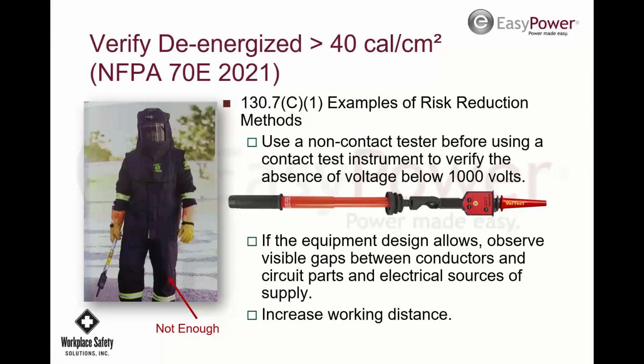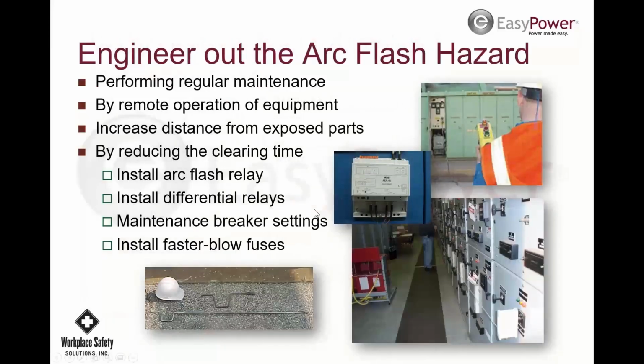So you'll do this first: check it at a known source, verify de-energized, go back to the known source, and when that all tests good, go up with your contact tester and test phase to ground and phase to phase readings. Do that live-dead-live as well. So that's an additional step. Mitigating the arc flash hazards: distance, again, is your friend.